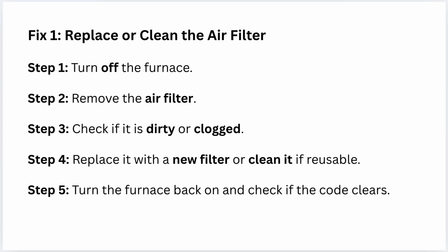Turn off the furnace, then remove the air filter. Check if it is dirty or clogged. Replace it with a new filter or clean it if it is reusable. Then turn the furnace back on and check if the code clears.